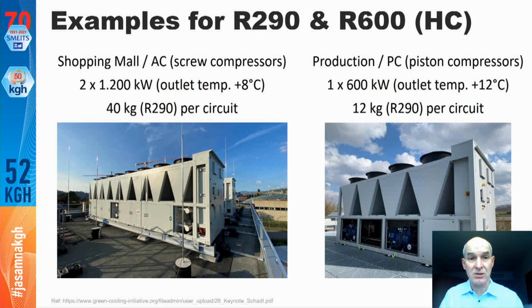These are large systems, examples from a German installation: shopping mall air conditioning compressors, condensing units, two times 1.2 megawatt with only 40 kilos of propane on the roof of the supermarket shopping mall. On the right you see a slightly smaller system, with only 12 kilos of refrigerant providing 600 kilowatts of cooling capacity.